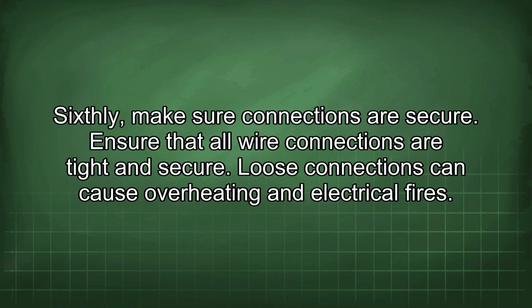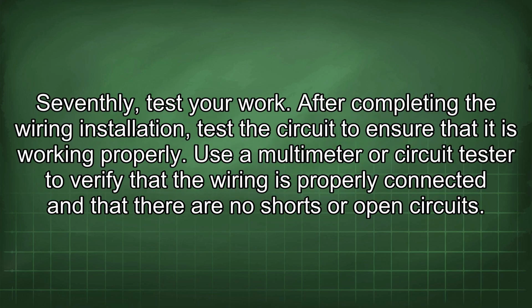Sixthly, make sure connections are secure. Ensure that all wire connections are tight and secure. Loose connections can cause overheating and electrical fires. Seventhly, test your work. After completing the wiring installation, test the circuit to ensure that it is working properly. Use a multimeter or circuit tester to verify that the wiring is properly connected and that there are no shorts or open circuits.